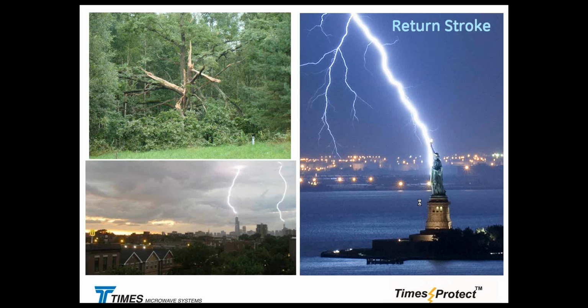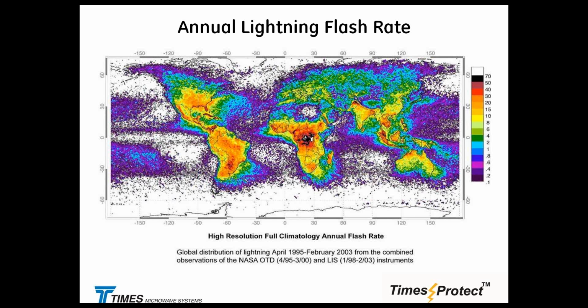Well, as I said, lightning will be purely statistical by nature, and if you take a look at the annual lightning flashes, the distribution of lightning events, it will be a very seasonal issue. So when we are going into winter in the northern hemisphere, the guys in the southern hemisphere are going to be suffering most. It will be changing with the seasonal changes and the geographical latitude of where we are located. If you take a look at the equator right here, these guys are just going through wet season, dry season year round, and the effects of it are shown right here on this graph. So basically it is statistical by nature. No two events are alike. Some of them can have two, three, four return strokes depending on how much charge we have to migrate. And with every stroke, the energy delivered to the communication site or anywhere will be directly proportional to the number of return strokes.